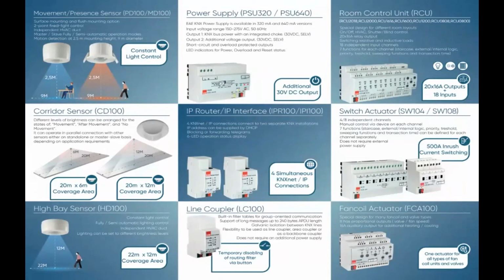Power supplies are available in 320 mA and 640 mA versions. And the beauty is that all these power supplies come with an additional 30-volt DC output, so an auxiliary output is available. You need not worry about projects where you might need the auxiliary output as well. With respect to the room controller units, which are the actuators, the on/off modules, they are available in 4-channel, 8-channel, 12-channel, 16 and 20 channels. The majority of the variants are available in 2 versions: one plain vanilla relay output module, and the second with binary input built into it. The one you see on the screen has 16 ampere outputs. All our relay modules have 16 ampere by default. There is no lesser capacity relay that we use on our relay modules. And this module has 18 digital binary inputs as well.